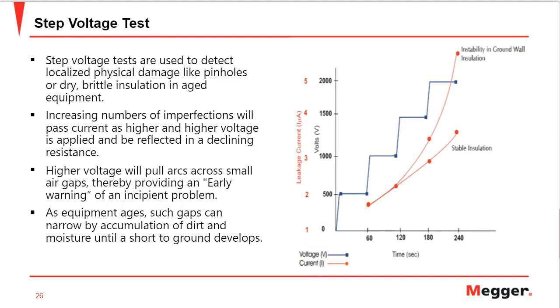It of course gives us a predictive, or incipient, understanding of the motor insulation, and we can take some actions on that motor before it gets into a failure zone. So it's just an early warning of an incipient problem, which we would understand from the results of the DC hypot test on the step voltage side.